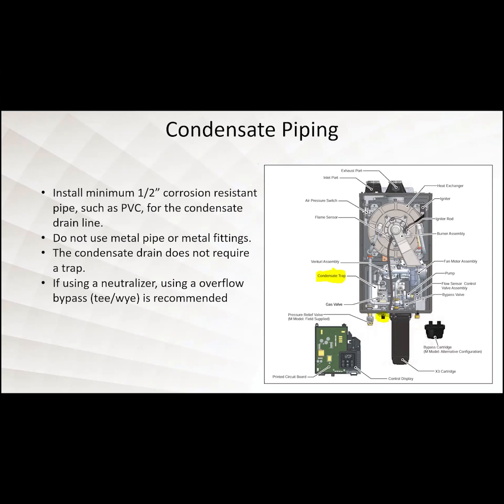I don't know if you guys have ever been out to a unit where it's had a condensate backup and it sounds like the water is boiling inside of that unit. But that's the sound you will get when condensate backs up inside of those heat exchangers. If you are using a condensate neutralizer with these units, if it's going on the horizontal, it pretty much is an extra P-trap. So what we suggest is when you come out of the condensate drain here, if you just add a T and put a little vent up off to the side, so you can introduce air into that system, it can flow through that neutralizer easily, and it will not lock up that system. So any questions on that condensate piping?